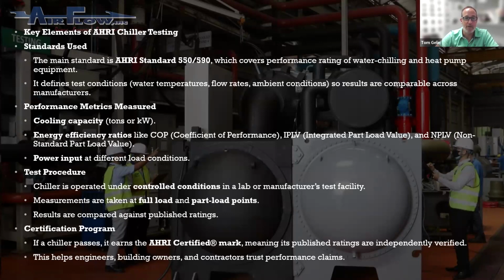In Florida, we can do a run test. We don't have the ability to do a climate controlled air cooled run test. So if you want specifically an air cooled test at 95 degrees, we're going to lean on the ambient temperature to get you close. That's the only real caveat I'd say about test procedures, but I would just use the test data that's listed in AHRI. It's a pretty stringent test. Anything to add there, Ahmad? Yep, we can do as per prevailing ambient, as Tom said. We don't have a controlled climate chamber. We have 3 certified AHRI test stands, 300, 500, and 1500 ton. For water cooled, we can do as per your design. We utilize the cooling tower.